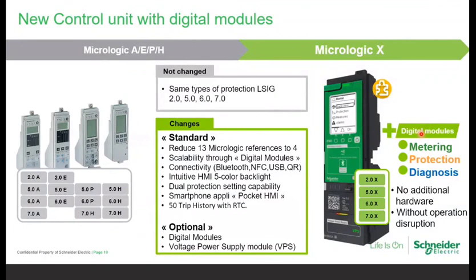So to give you one example, let's say you have a 6E release in your ACB, and if tomorrow you want to go for the reverse active power protection, then what do you have to do? You have to take out this E release, buy a P release from Schneider, install it in the NW ACB, so that your breaker will be 6P and it can give you the reverse active power protection. But this P release has got 10 other features in addition to the reverse active power protection, but you need only one protection, that is reverse active power protection, and still you need to pay the cost of the entire release.